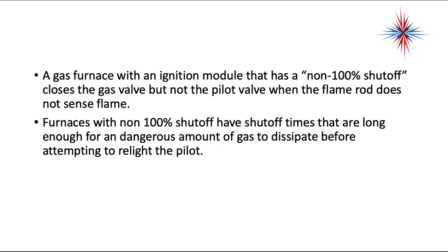A gas furnace with an ignition module that has a non-100% shutoff closes the gas valve but not the pilot valve when the flame rod does not sense flame. Furnaces with non-100% shutoff have times that are long enough for dangerous amounts of gas to dissipate before attempting to relight the pilot.